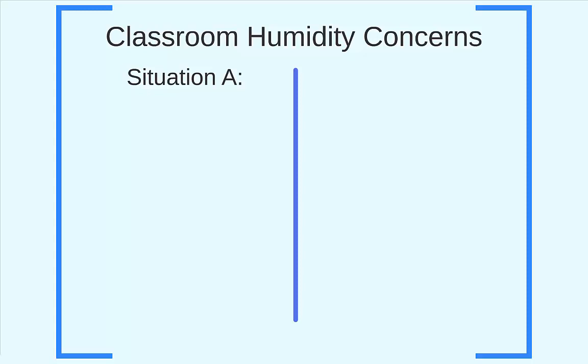Since the room's VAV box is only controlling for temperature though, there may be some ramifications when it comes to humidity levels in the space if we get too aggressive with the supply air temperature reset schedule. For example, students put off about 110 BTUs per hour of latent heat energy just by breathing.